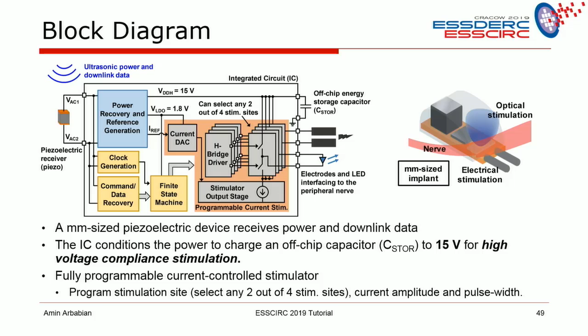Off-chip capacitor, off-chip electrodes, we specifically designed for this application. We have to design electrodes that are non-active in the biochemical interface, so usually platinum electrodes or platinum black electrodes. Then you have LEDs for stimulation, and then you have the piezo. These are the off-chip components sitting outside. So this is what the chip looks like.